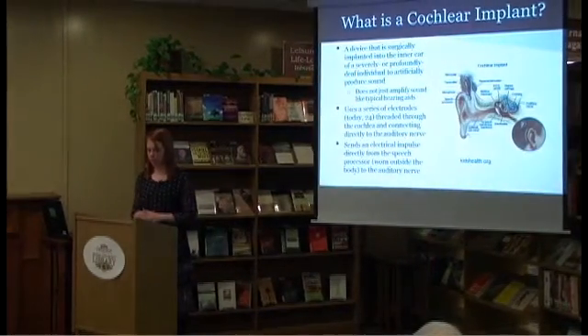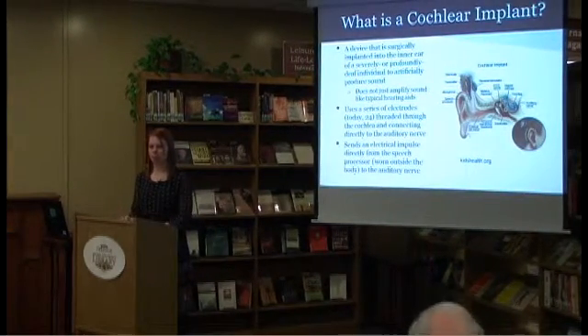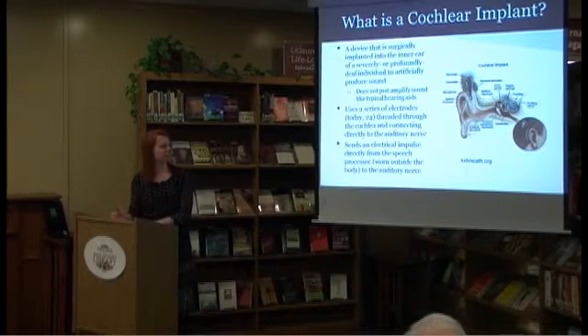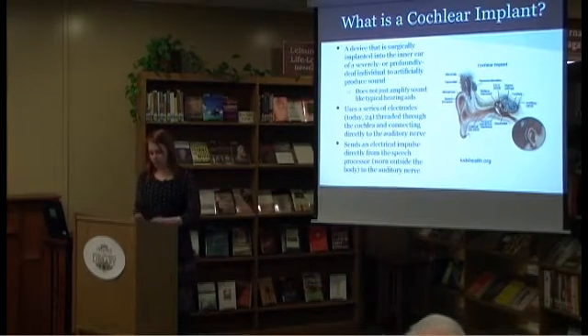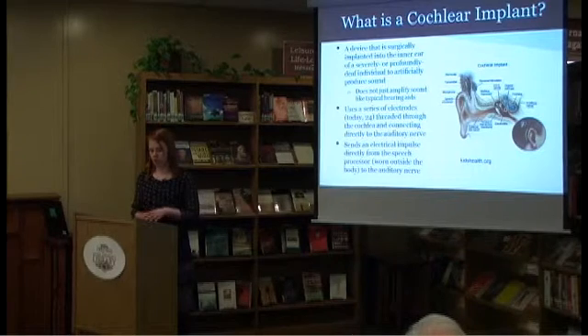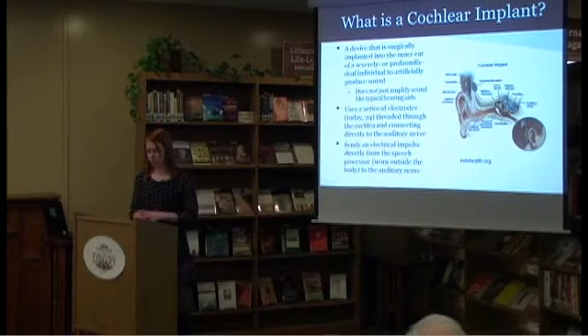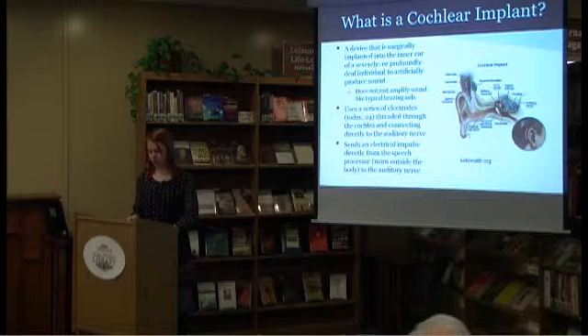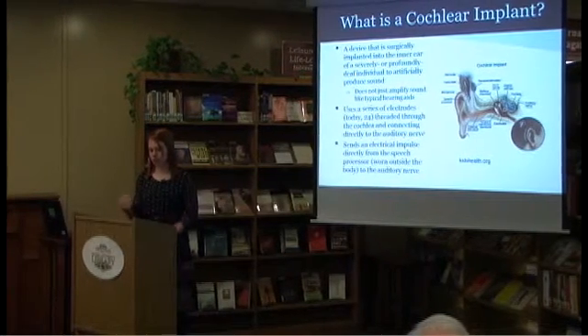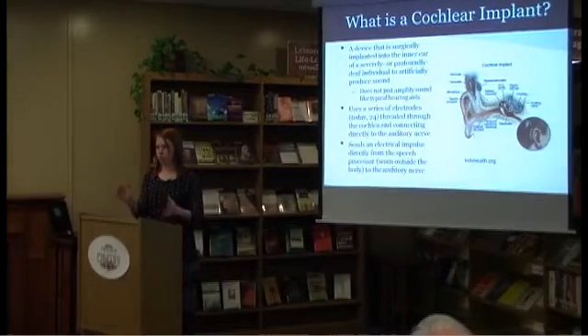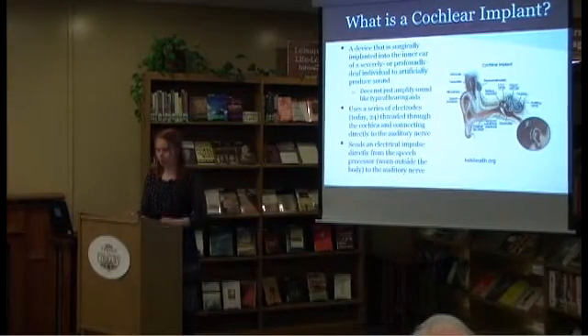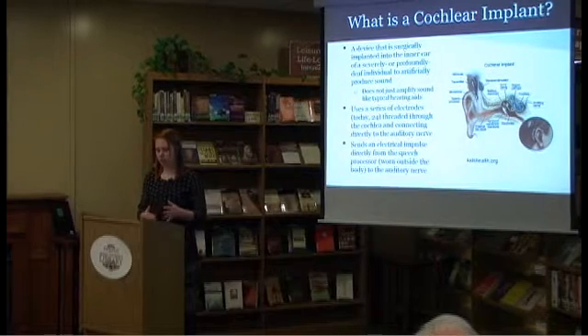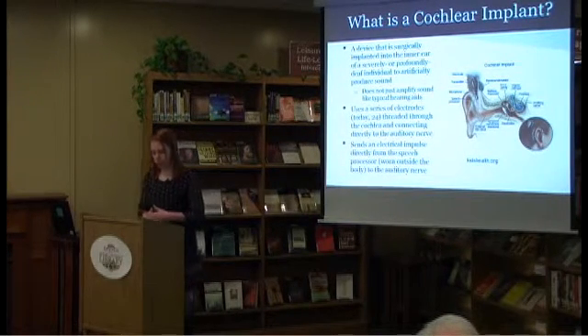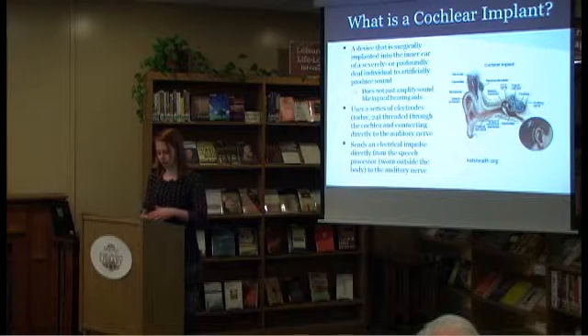First, I would just like to define what is a cochlear implant. A lot of people don't really know what this device is. It is a device that is surgically implanted into the inner ear of a severely or profoundly deafened individual to artificially produce sound. Unlike typical hearing aids, it doesn't just amplify sound, it actually creates artificial sound. It uses a series of electrodes. Today they use 24 electrodes threaded through the cochlea and connecting directly to the auditory nerve.